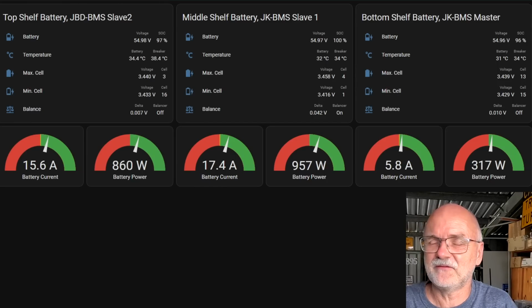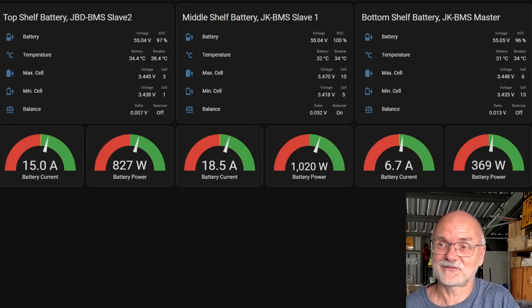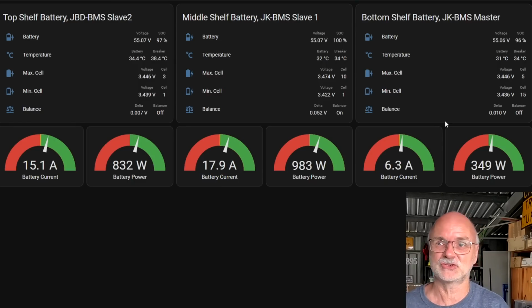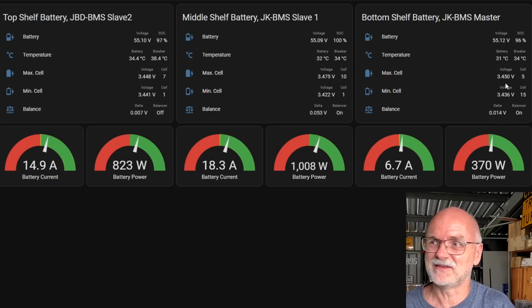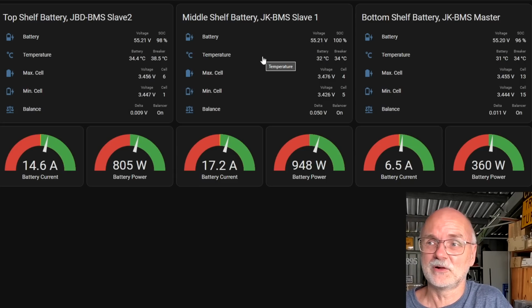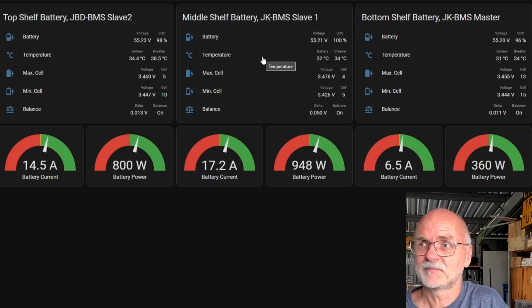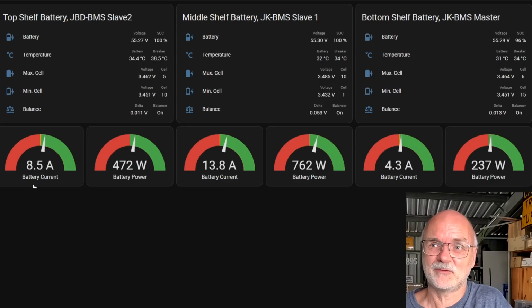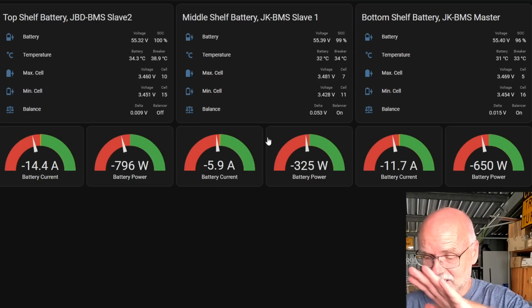So we are now reaching 55 volts, but you can also see that the balancer has turned on in the middle shelf battery while the other two balancers are still off. We only balance if we are over 3.45 volts and over 10 millivolt deviation across these 16 cells. This is what we have just here in the bottom shelf, 10 millivolt, but none of the cells is actually over 3.45. Now it turns on, and now the 0.6 amp balancer is actually working. 3.45 we have just reached, and we are balancing. But now we are hitting 55.2 volts, which is our maximum charge voltage for this battery. Look how quick the current is going down here on the top shelf battery at 55.2 volts - it is absorbing quickly. All right, enough with this testing now.